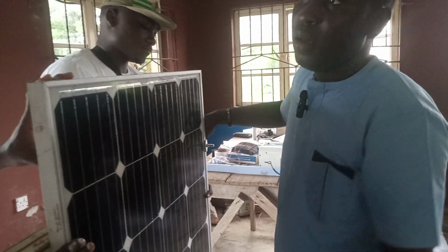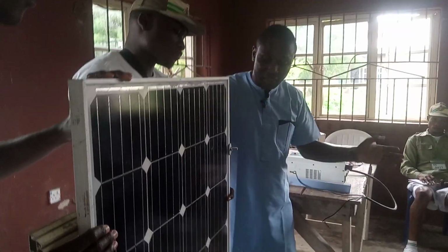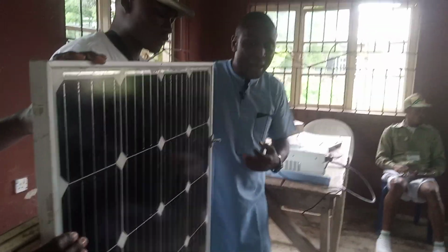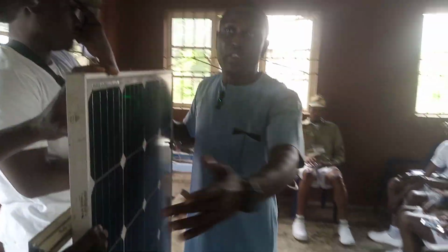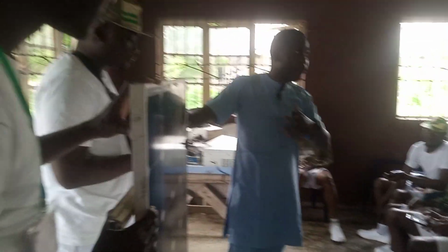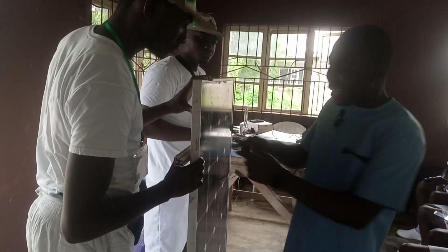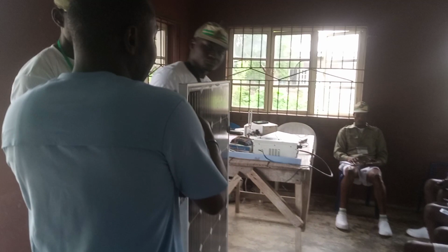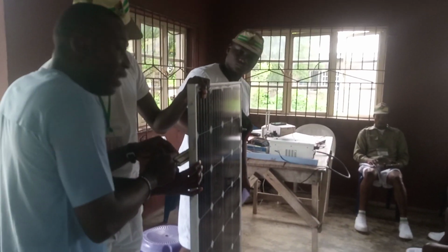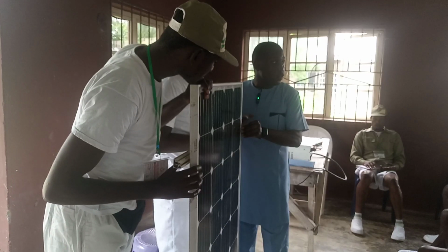Yeah. There's another thing we call stop railings. Maybe tomorrow I might discuss. Stop railings are the railings that you put at the extreme end of your panel. And maybe I should use this opportunity to explain railings very well. If you don't have stop railings, you can cut out of this normal railings. You measure the standard length of this panel, this length here. You cut the same length and put it at the other end here, so that it can be firm.